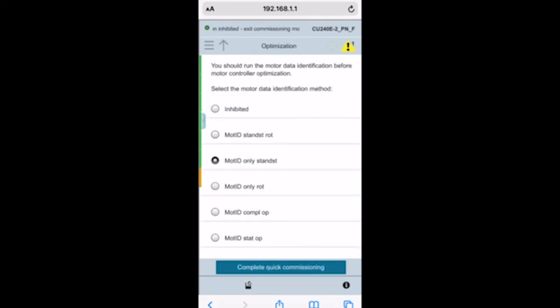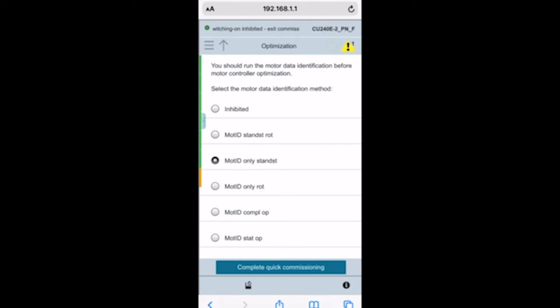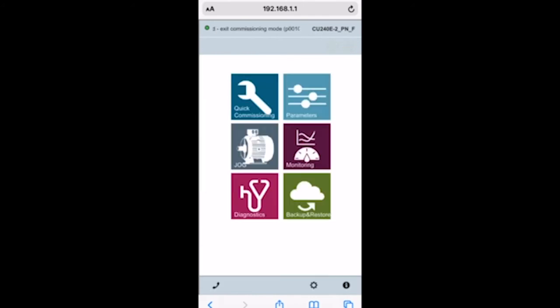Finally it's going to ask for your motor ID. There's a couple different options here that you can select. I always recommend to people to do a motor ID because every single motor from any manufacturer is going to be different. But for this demo purpose, we're just going to select inhibited. With that, we've now commissioned our drive.